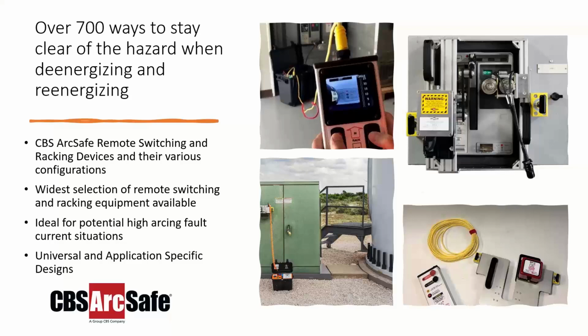If you look at the photos here, you'll see a single use racking device for a Magnum DS breaker on the top left side. Right next to it is a charge trip close actuator for a Magnum DS breaker. It pushes the trip and close buttons.